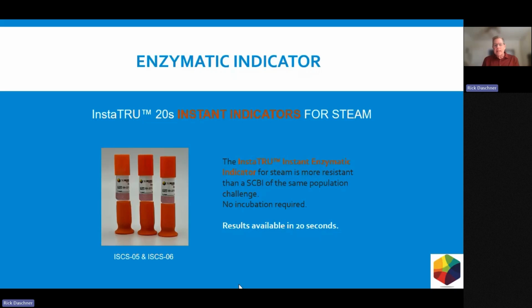And not to mention, once this becomes considered a biological indicator, at least for the U.S. market, this will speed up getting instruments back to, let's say, an OR, where they're standing there with a patient under anesthesia waiting for this to come back. This will give them an instant result once they get the sterilization process completed. We're excited about this product, and we're more excited about getting our biological indication soon. But right at this point, it's changed the way a lot of research labs and some in waste disposal contamination approach their business.